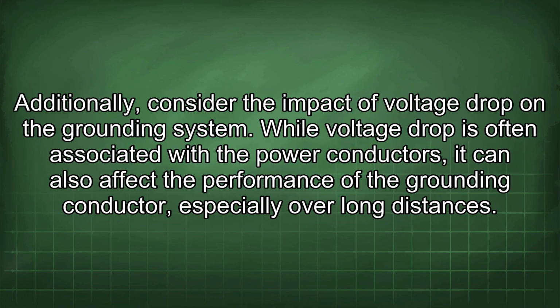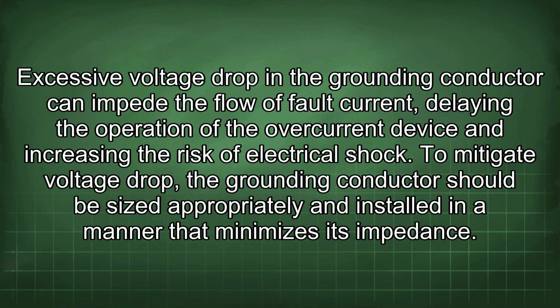Additionally, consider the impact of voltage drop on the grounding system. While voltage drop is often associated with the power conductors, it can also affect the performance of the grounding conductor, especially over long distances. Excessive voltage drop in the grounding conductor can impede the flow of fault current, delaying the operation of the overcurrent device and increasing the risk of electrical shock. To mitigate voltage drop, the grounding conductor should be sized appropriately and installed in a manner that minimizes its impedance.